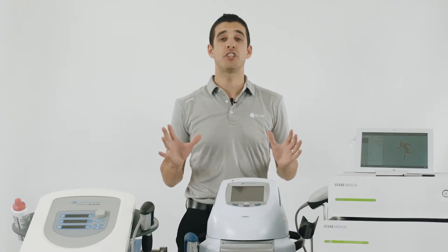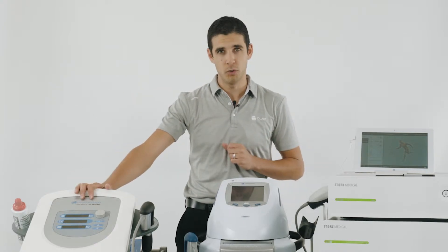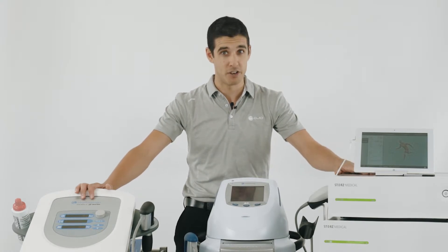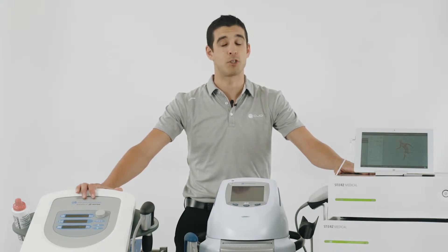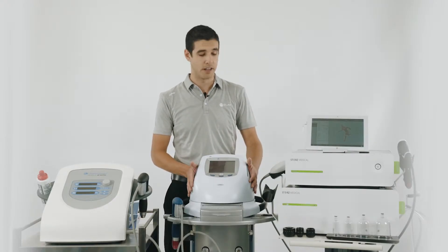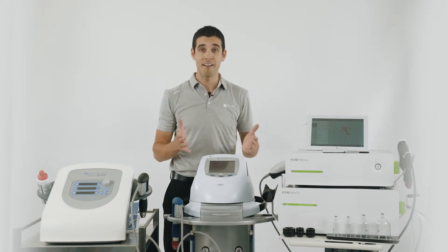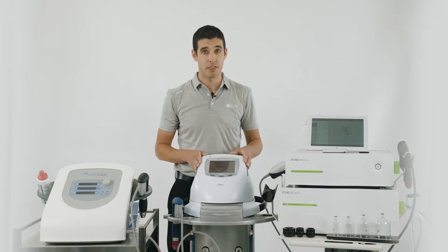The first feature to compare is the bar pressure. The Chattanooga Mobile 2 has the same compressor as the Storz Medical MP100 — they both go up to 5 bars, however there is a trade-off: the frequency only goes up to 12 Hz at 5 bars. The Chattanooga Intellect Clinical shockwave machine has a very similar compressor to the MP200. Both machines go up to 5 bars at 21 Hz, and with the V-Actor will go up to 35 Hz.